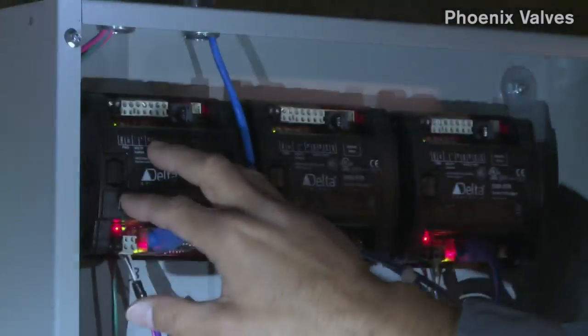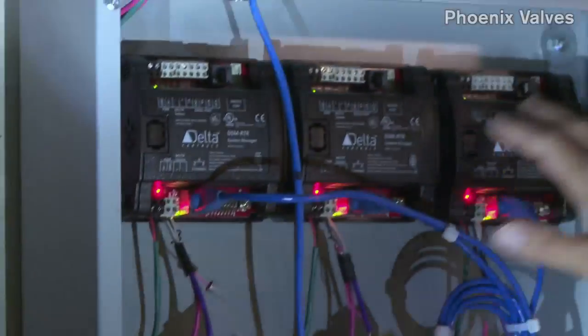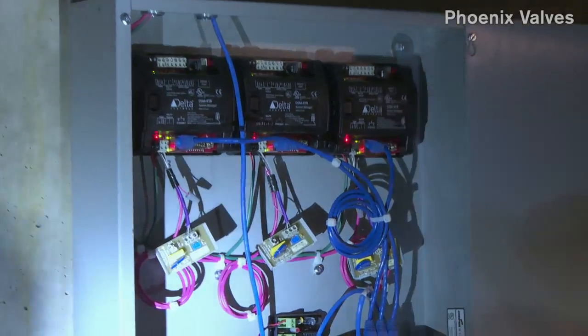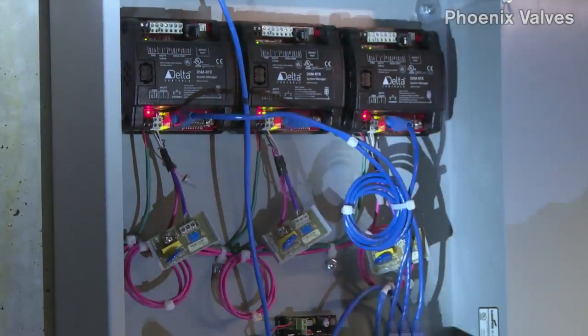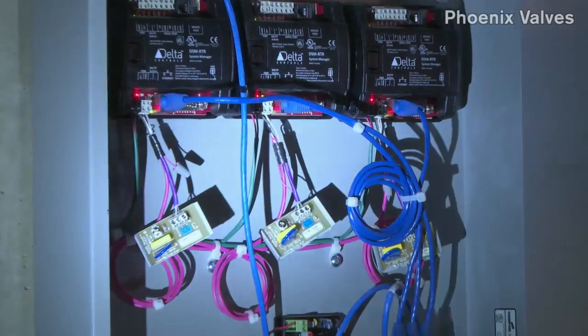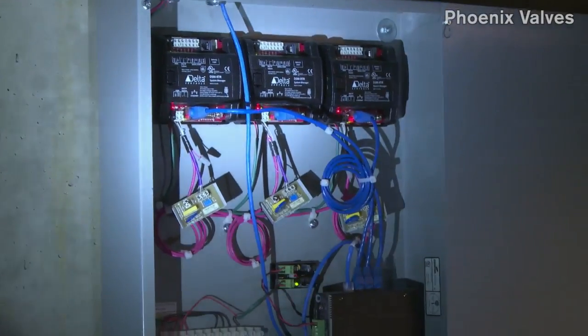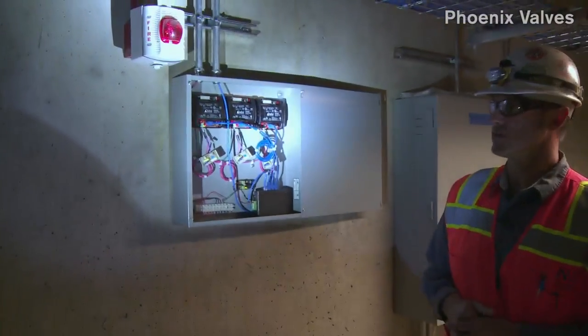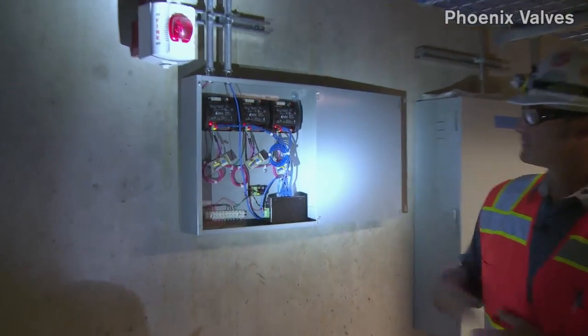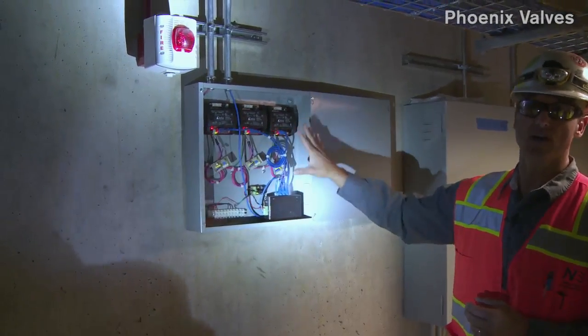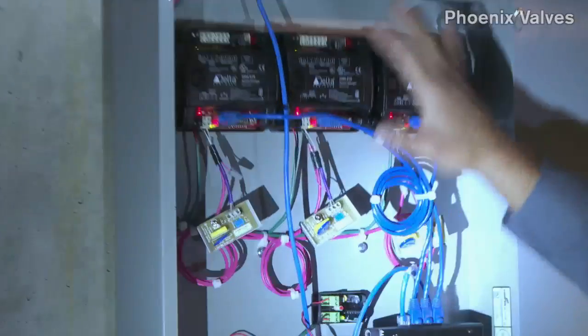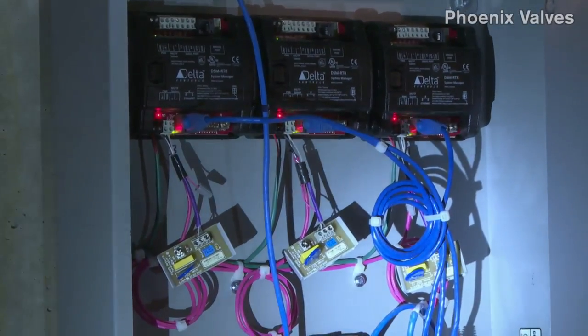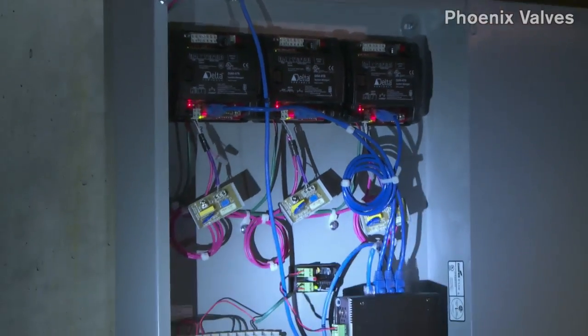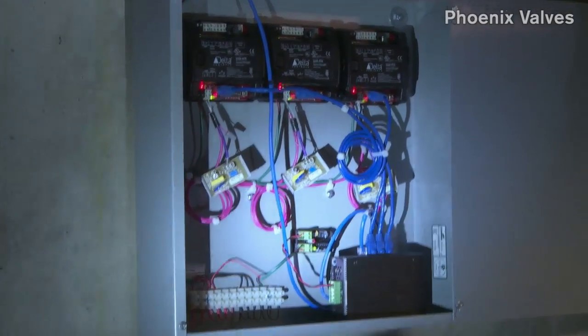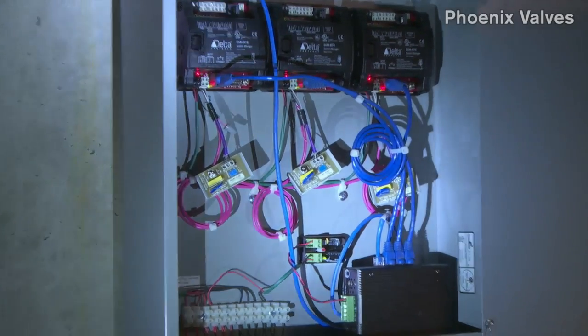So in there it should say which Phoenix valves will be on this router, which one will be on there, and that's where all the code is written to tell the corridor valves to increase or decrease depending on if they go positive or negative. And then that ties into Johnson Controls as well. So this is pretty much the only Delta routers in this vivarium. It's all right here in this location as you first come into the vivarium, so you don't have to go searching through everywhere. And I think that's pretty much it for the Phoenix on our side.